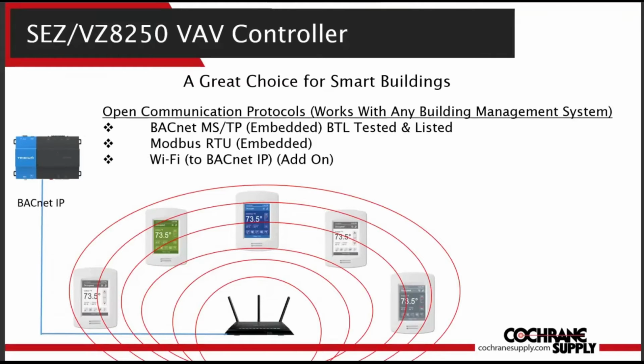In a standalone application, the 8250 can be configured to notify or alert the appropriate parties via email of malfunctions like temperature, humidity, or CO2 values that are out of range, or if there's been a fault or a dirty filter alarm. A BMS or supervisory device is not required, essentially letting you know of a problem so you can react and perform the necessary maintenance.